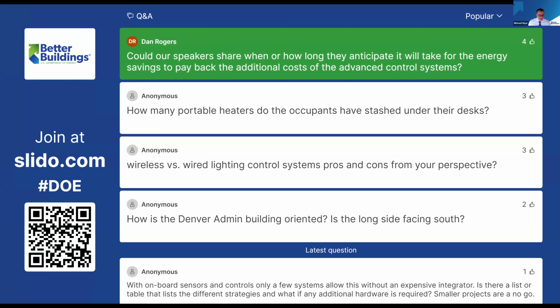I'll step in for a second. We've done a fair amount of different studies on this. Let's start with the lighting system: once you add advanced LED controls onto the LEDs, it often pushes the payback or cost recovery period for the lighting system to more than 10 years, depending on a few variables. We've seen that integrating with the mechanical system reduces the payback of the lighting system by 30 to 40%. Many of the integrations we've done, looking at about 7 of them, showed a payback from just the setbacks on the mechanical system of between about 2 to 3 years. Most of these involved small mechanical work, some labor, and a few pieces of equipment to make the communication work, but no major installs.